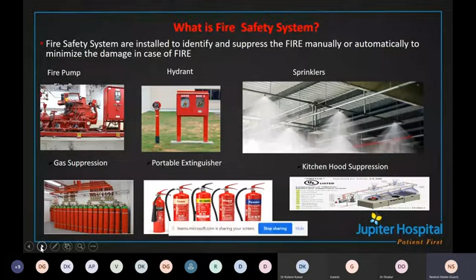But if there is a fire there, a fire suppression system is involved. This is very, very important: advanced heat detectors are installed inside the hood, which trigger only in the case of fire. And this type of system is very, very important if you want to keep control of a sudden fire on the kitchen or pantry side.